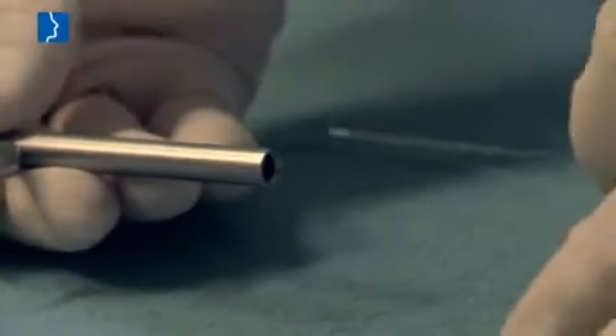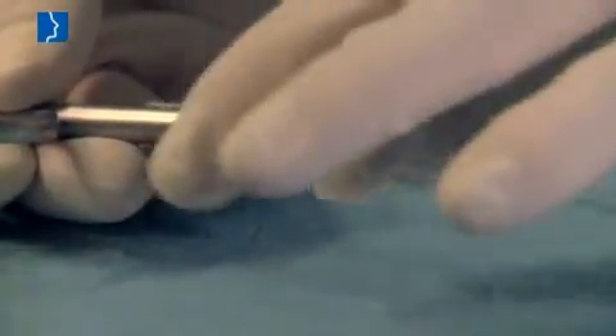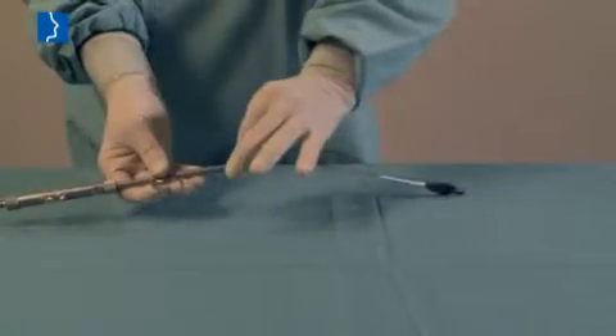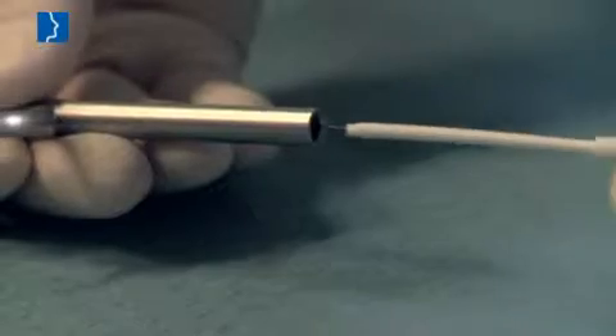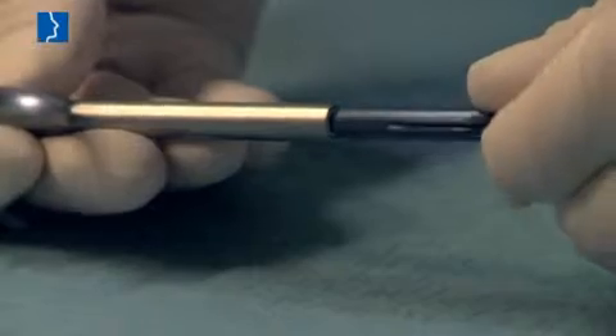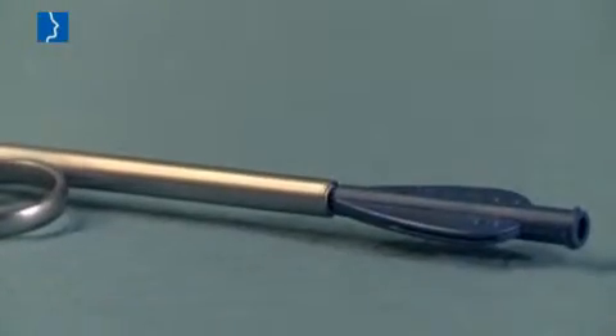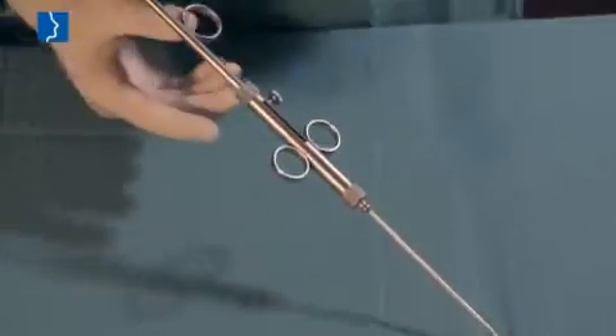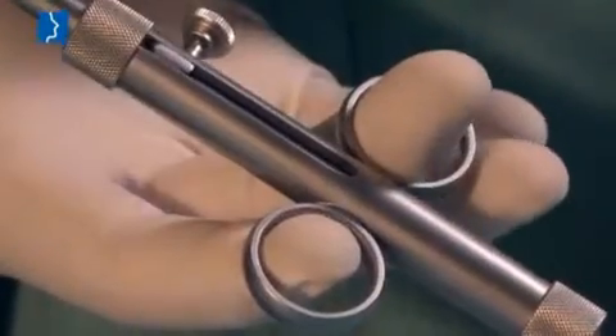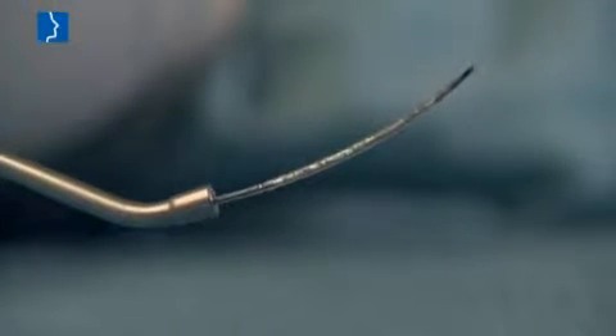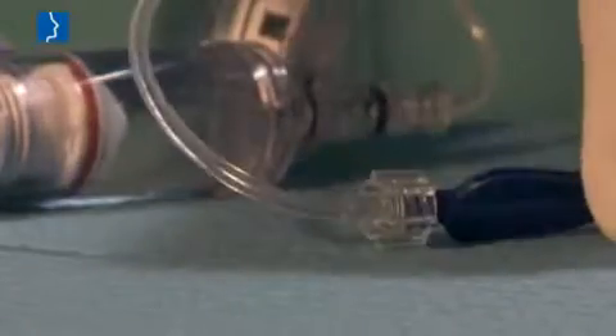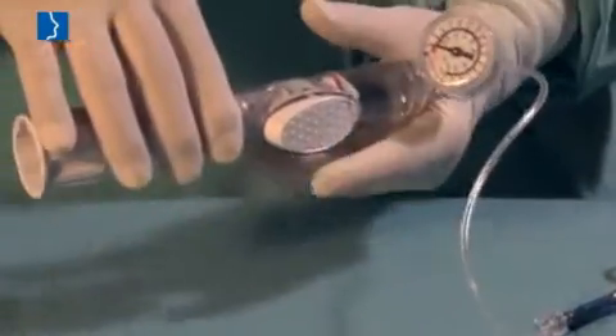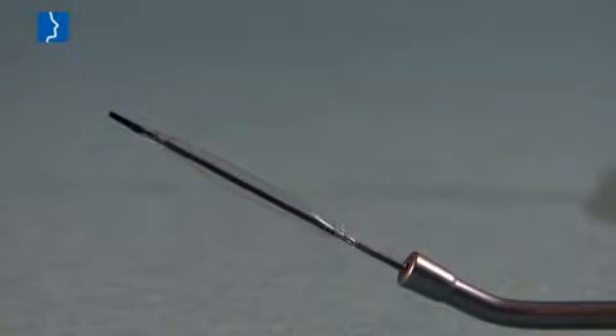Then insert the catheter into the insertion instrument, making sure that the white shrink tube has been inserted completely. This way it's guaranteed that the balloon is inserted into the eustachian tube in the defined length only and does not damage the mucous membrane in front since it's completely contained in the instrument. During the operation, the balloon catheter is pushed forward within the insertion instrument. Connect the inflation pump with the catheter either prior to or during the operation. For actual dilatation, put a pressure of 10 bar on the balloon catheter.